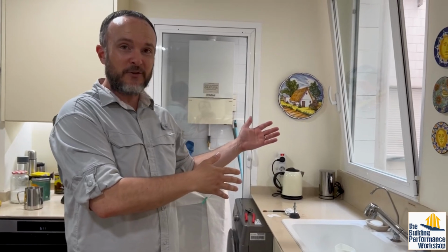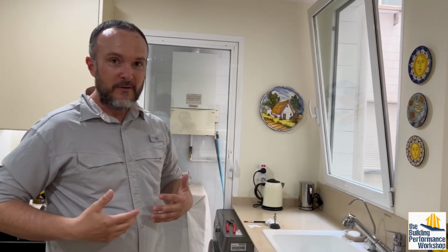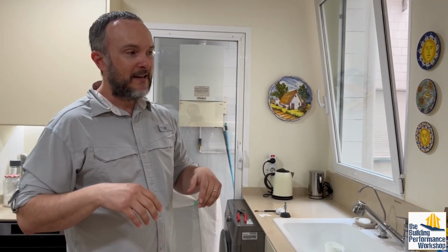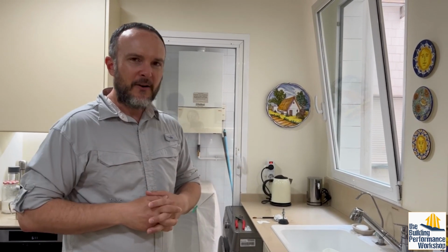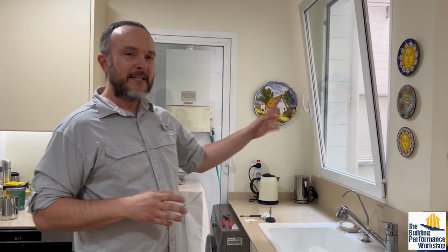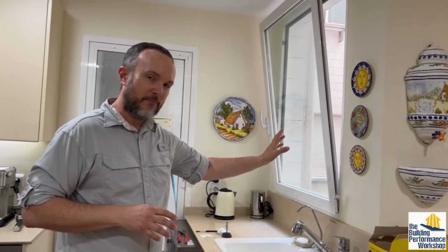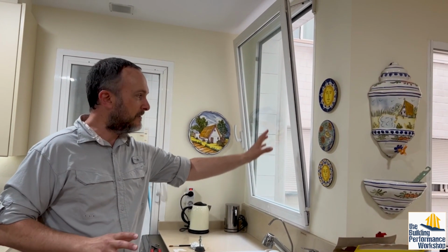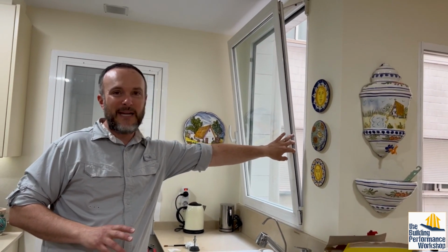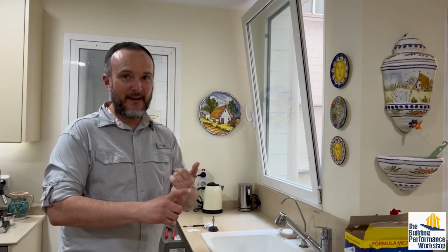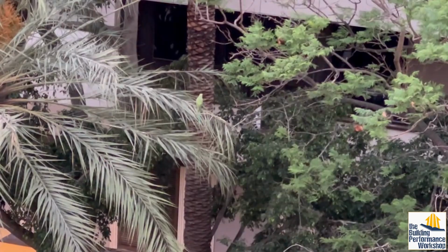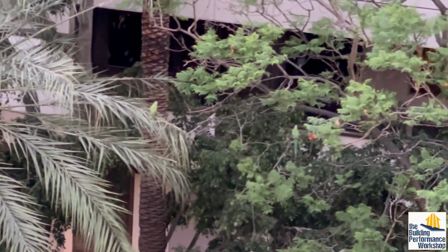When you use natural ventilation like this to bring in the fresh air from outside, even though we're in a city and it's city air, it is important to have dilution air because the indoors is more polluted than outside at certain times. This is an important feature, but we can't control for all of the things. We're not filtering any of the air coming in, we're not conditioning it, and we're not screening it for bugs and critters or parakeet feathers, which float through sometimes.